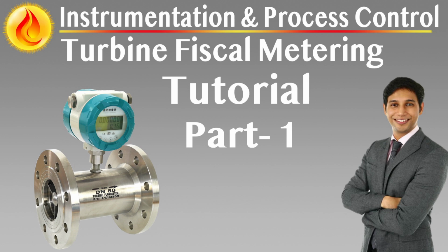Metering run architecture and functional integrity. Parallel run configuration for redundancy and turndown. Each metering run operates as a self-contained measurement line engineered for accuracy, redundancy, and maintainability. Runs are arranged in parallel to handle a wide turndown range and to ensure uninterrupted operation during proving, maintenance, or fault isolation. Design typically follows 2 times 100% or 3 times 50% configurations to provide both capacity and failover flexibility, while minimizing rangeability degradation during partial load scenarios.